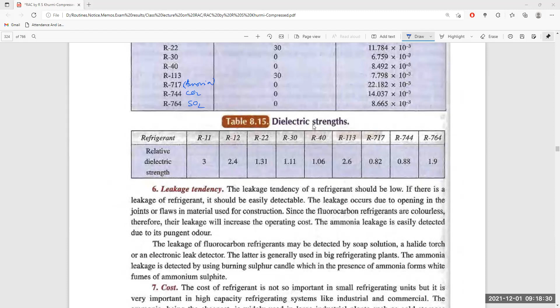For ammonia, leakage is easily detectable as it has a pungent smell. The leakage of hydrofluorocarbon may be detected by soap solution. The latter uses a Halide torch and an electronic leak detector. The electronic detector is generally used in big refrigerating plants. The ammonia leakage is detected by using a burning sulfur candle in the presence of ammonia, from which white fumes of ammonium sulfite form.